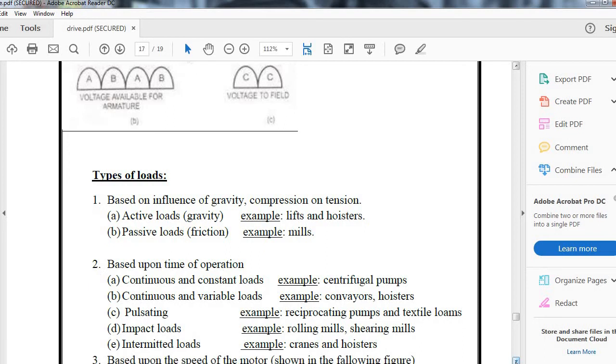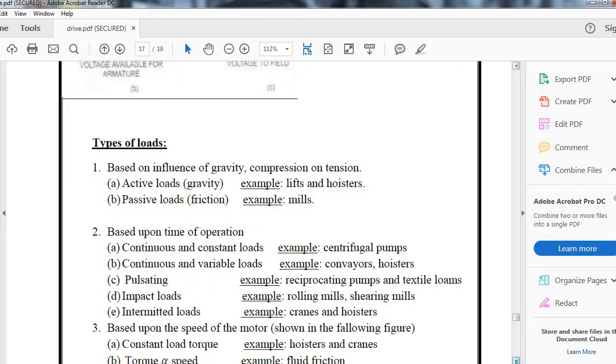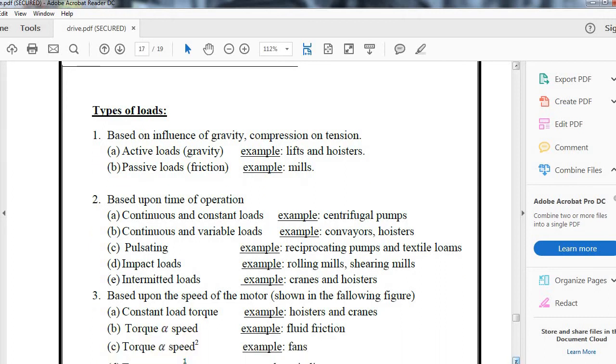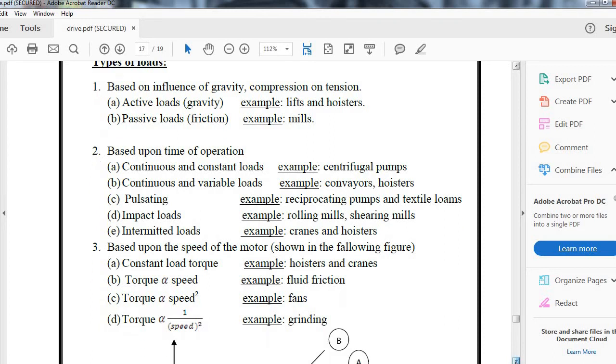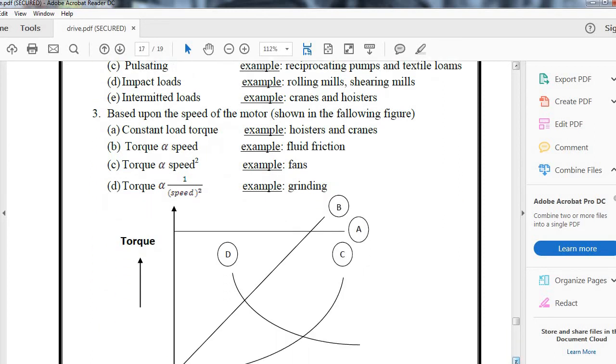Based upon the speed of motor as shown in the following figure, we can have constant load torque, torque from fluid friction, torque directly proportional to the square of the speed (for example, fans), or torque inversely proportional to the square of speed (like grinding).